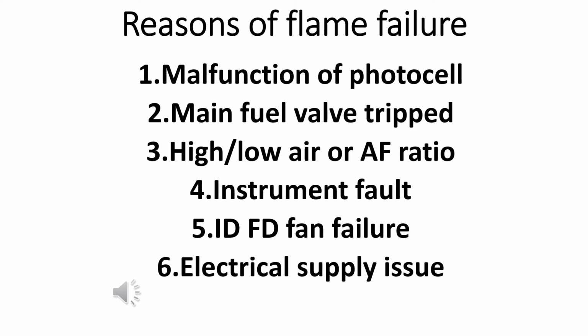And number three is the air fuel ratio. If your air fuel ratio is disturbed, or the flow of air is high, or the flow of air is low as compared to fuel, then there will be trouble to the flame, and the flame will fail. Number four is the instrument fault.